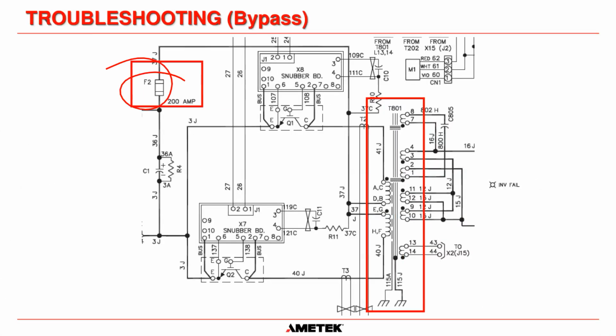And if F2 fails, then it could be that there was an IGBT failure. Or one thing you could also check is that the ferro-resonant transformer hasn't overheated. It usually will give you indication over a long period of time that the transformer is going to fail. It starts to make a lot more noise than it used to, starts to heat up. So that's why we always perform thermo imaging on all of our transformers during our annual PMs. But what can happen is one of these windings here can short down to ground. And if that happens, then that is going to blow this fuse every single time.